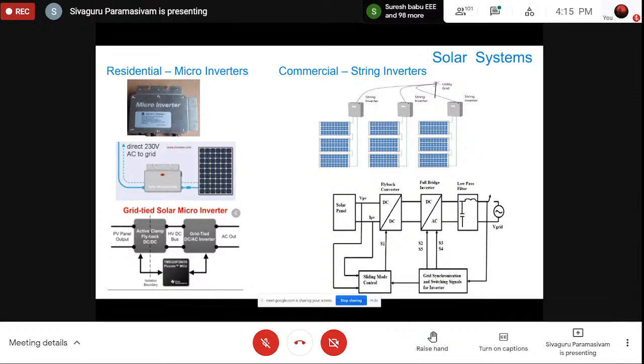So why are harmonics generated from these kinds of systems? You know very well, all these power electronics are nothing but switches, like the switches that we have in our home: when we switch on, the electricity passes, and when we switch it off, it goes off. But what is the difference between that switch and the power electronic switch? This is an ultra high speed switch, so it can operate in the range of 5,000 to 6,000 hertz, kilohertz even. That's what we call a switching frequency. With that kind of high speed switching, we get the power conversion and whatever the required profile of waveform that we need in the application.